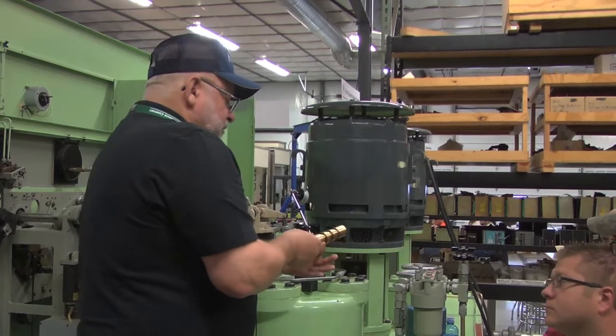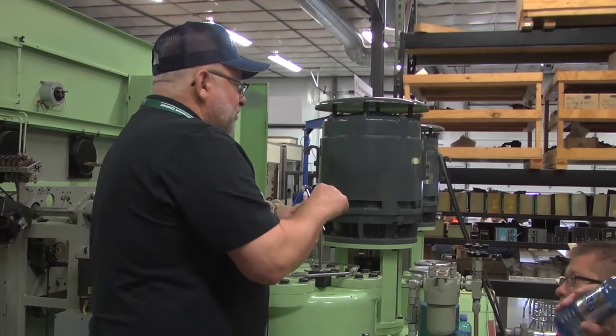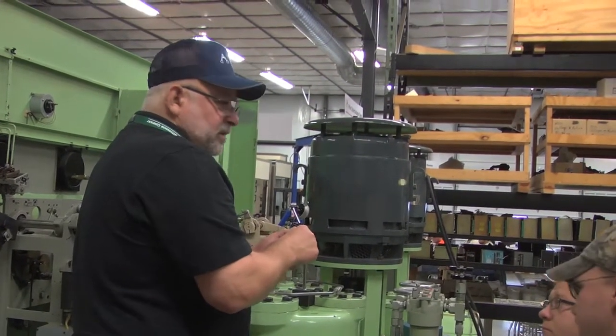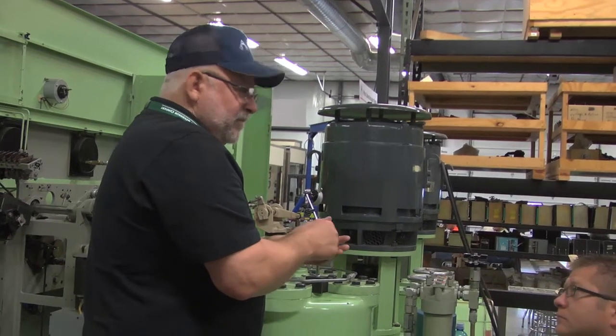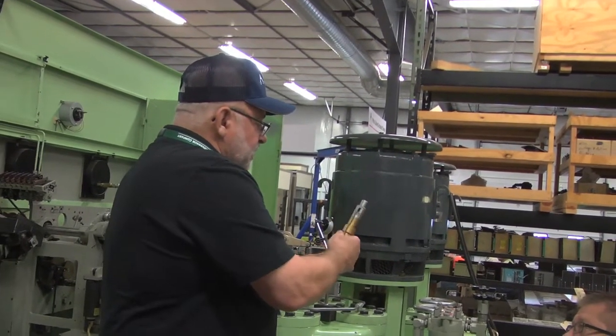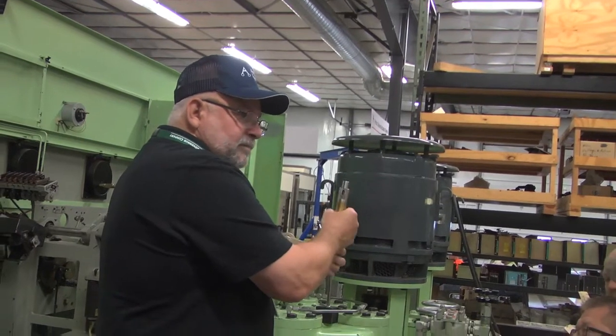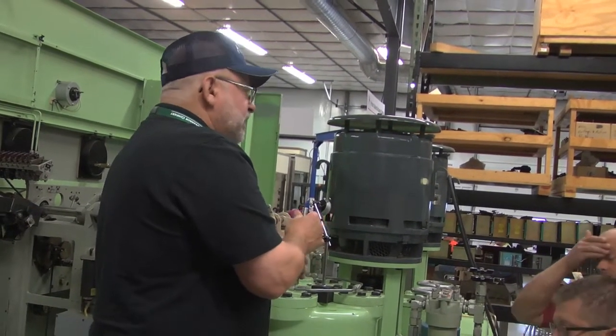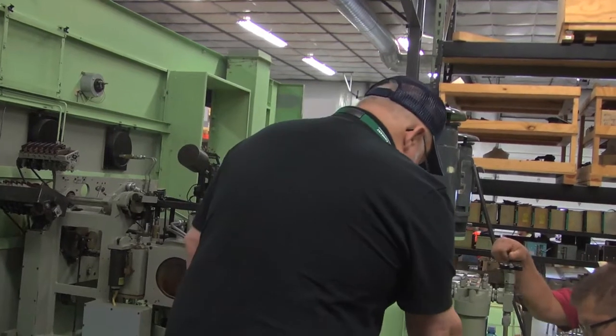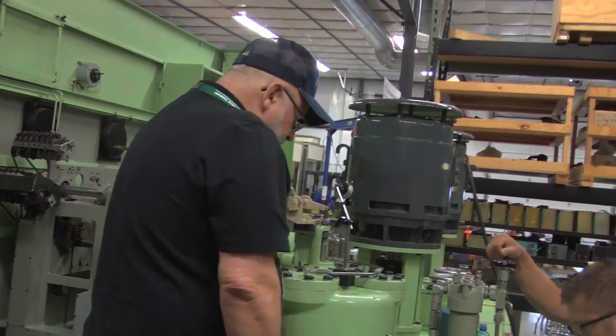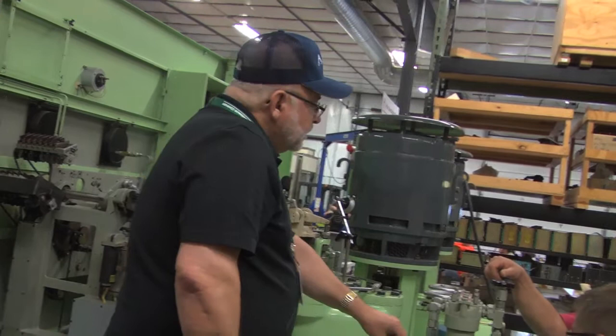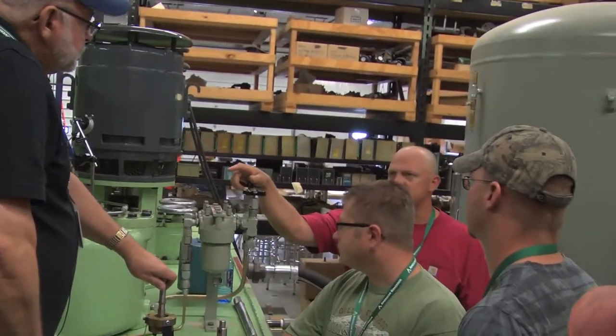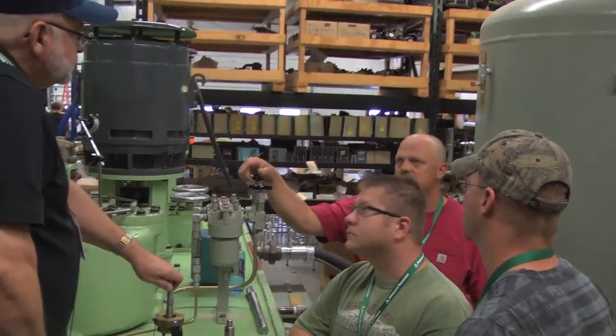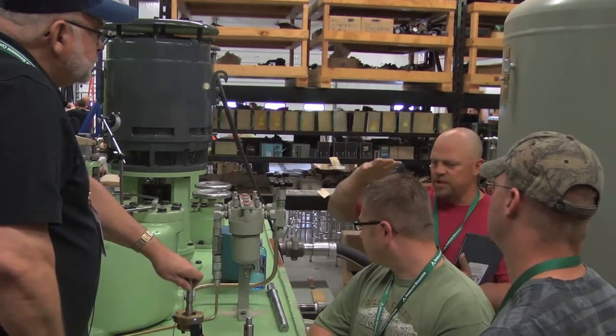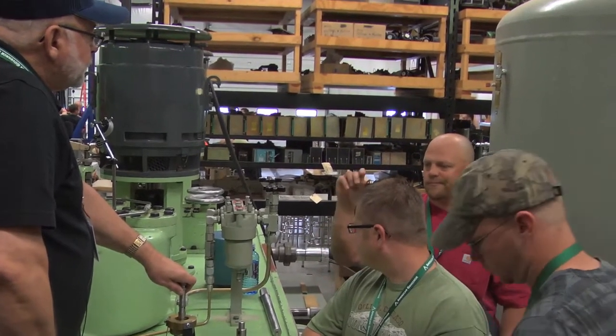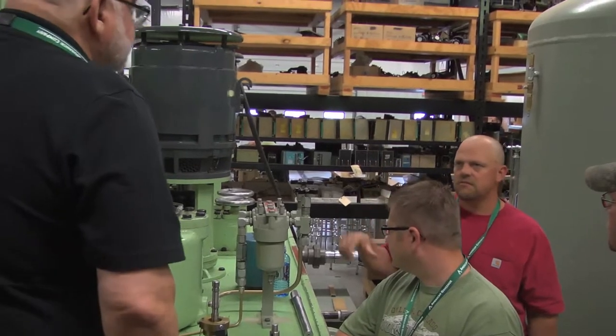And I've seen these vary. I've taken 3 of them that are supposed to be the same, and there's 10,000 difference in everything. Yeah. The main thing is keeping them clean on the outside, you know. Clean them up. And clean oil is key to every governor. We just did a big upgrade on our oil systems on the sumps. We put those CC Jensens. We put those big pleat paper. They're like an organic filter.